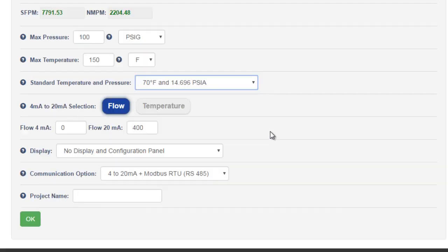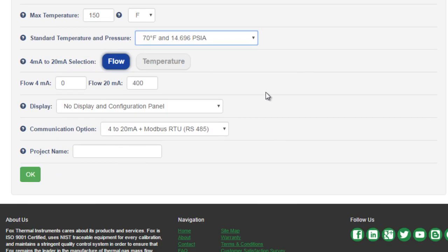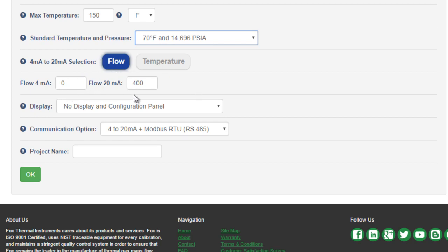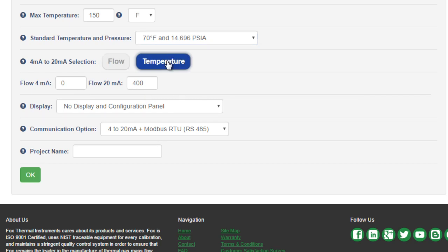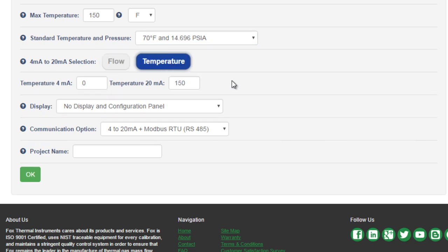After the process data, we need to configure the hardware of the meter. The first step is choosing what the 4 to 20 milliamp output will be configured for, flow or temperature. The default setting is flow and the default values are from 0 to your application's maximum flow rate. If we switch to temperature, the default setting will be from 0 to the maximum temperature of the application. We'll leave this as flow.